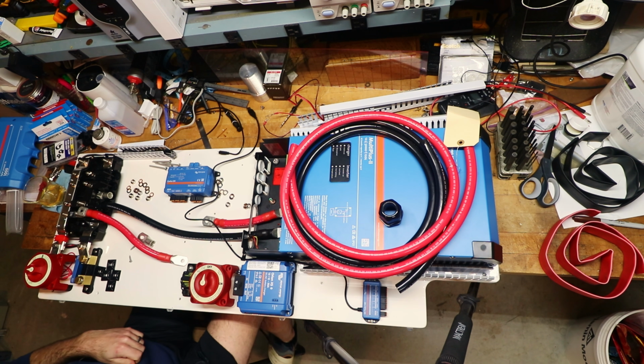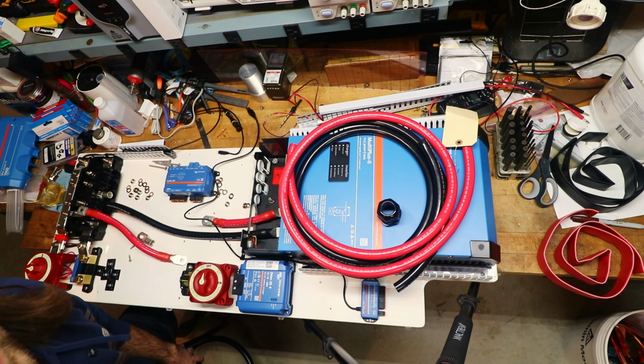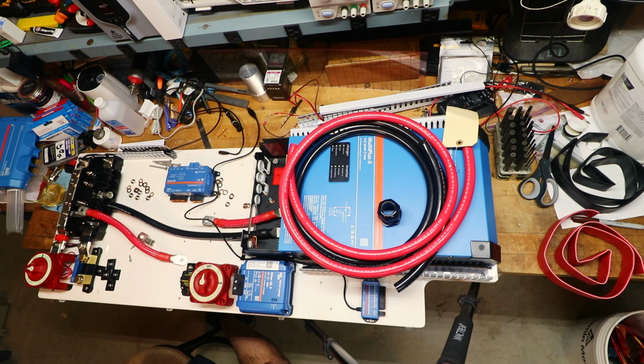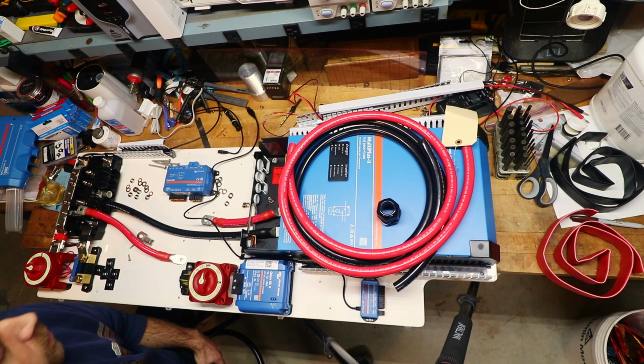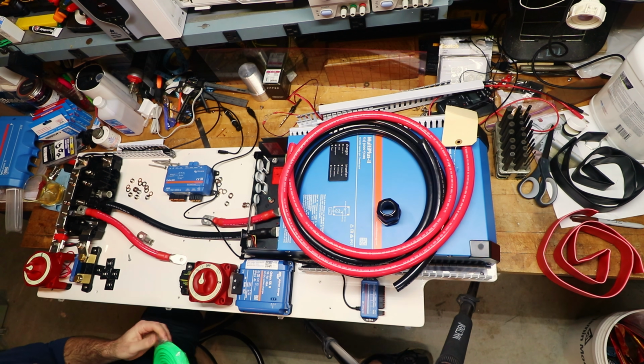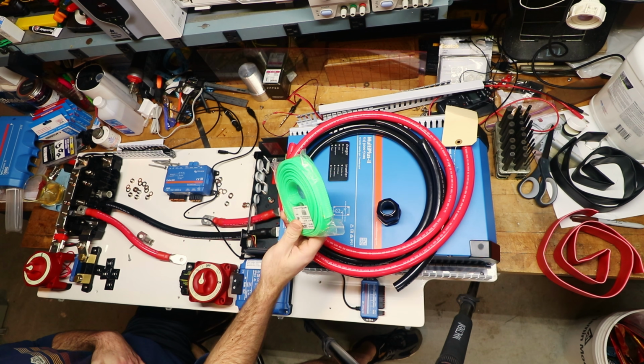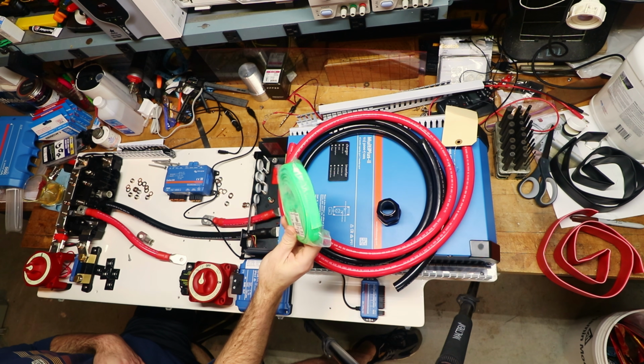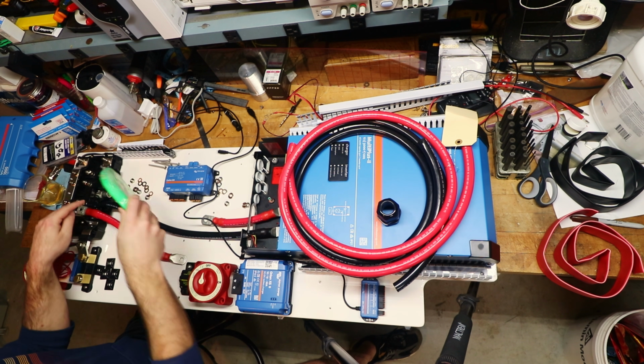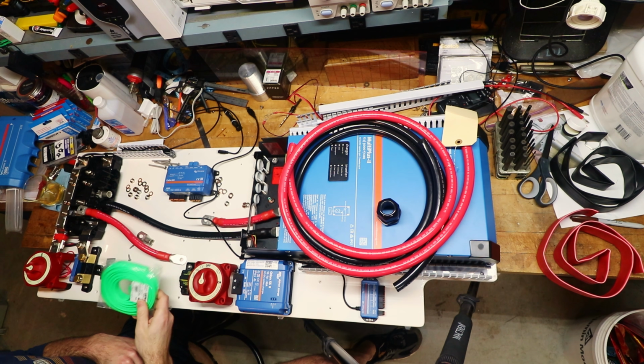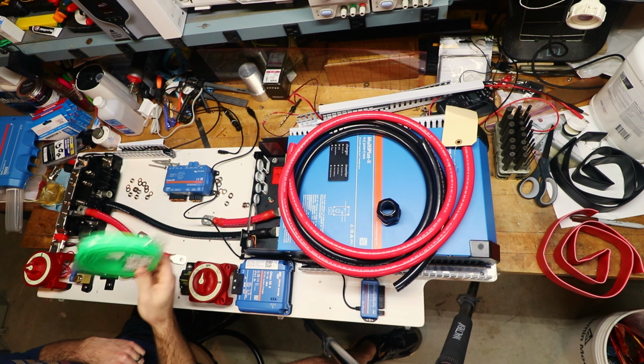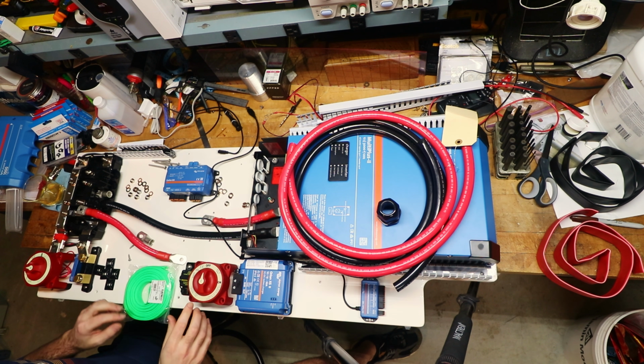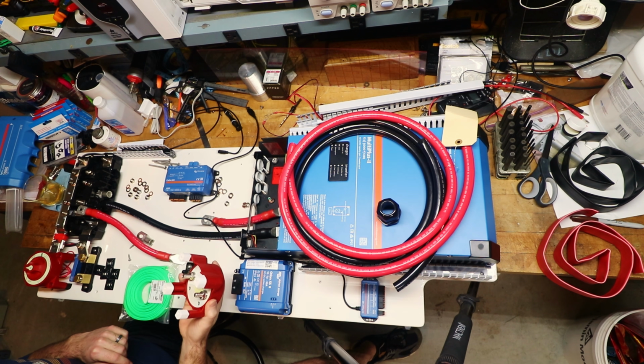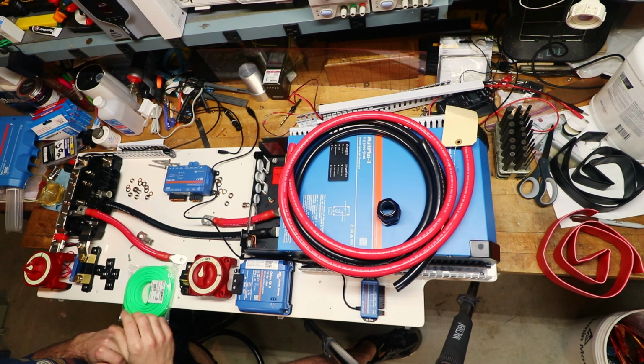Typically that's going to be a green conductor for an equipment ground. However, I didn't want to buy one small piece of green wire, so what I did is I bought this green expanded sleeving. At this point, I'm going to cut this chassis ground conductor to length, crimp the terminals on, get this flex sleeve on, and then we'll install those conductors permanently, get them torqued down to spec, and see what that looks like.